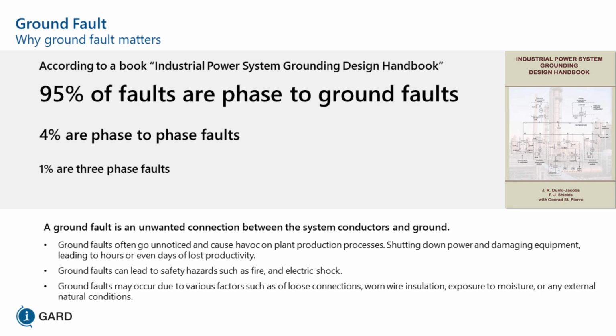So, ground faults and system grounding. According to the Industrial Power System Grounding Design book, written by Dunki-Jacobs, Shields, and Conrad St. Pierre, 95% of faults begin as ground faults. 4% are phase-to-phase faults. 1% are three-phase faults. The 1% three-phase faults that occur are not necessarily three-phase faults, but they're always more or less caused by human intervention. Think of a forklift driving through a bus duct. That's a three-phase fault, but it's caused not by the deterioration of the system, but by human intervention.